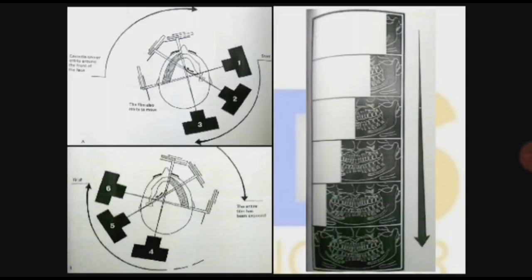On the right side, first the most posterior part of the left side is formed, then a little bit more in position 3, then from position 4, 5, 6, and the entire image is formed in 6 steps. For ease of understanding, only 6 steps are shown, but actually they are very small millimeter steps. When the machine moves, it's continuous in multiple steps, not only 6 steps.